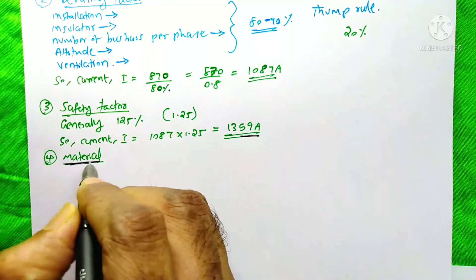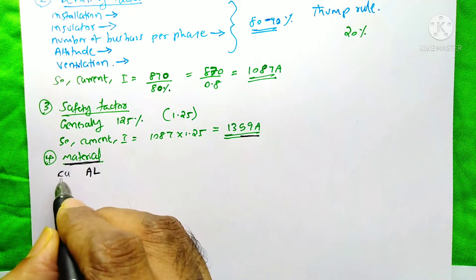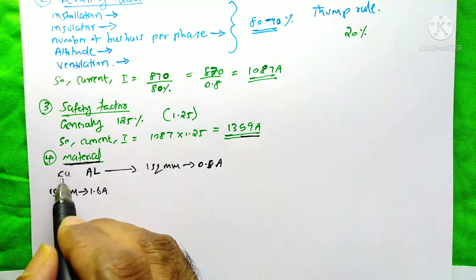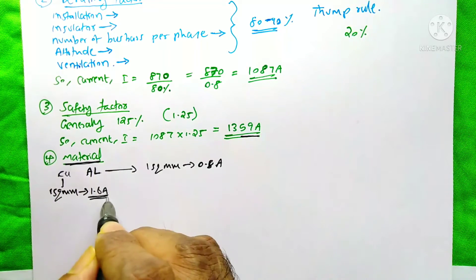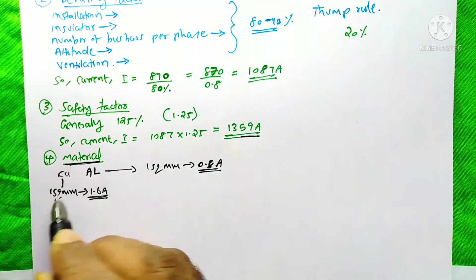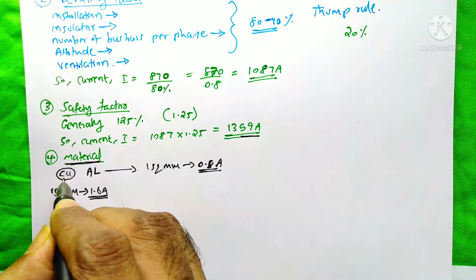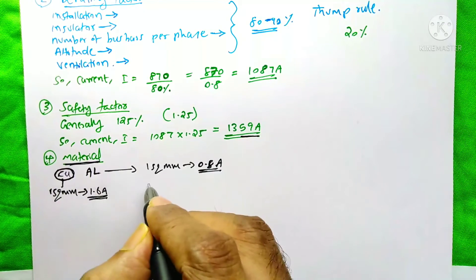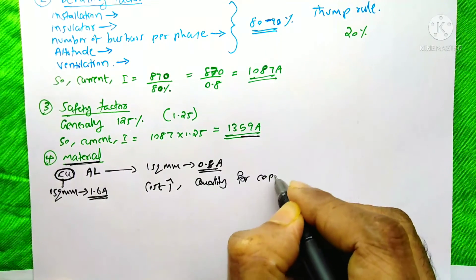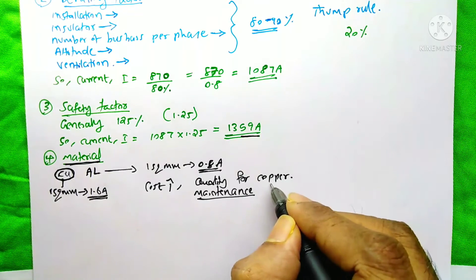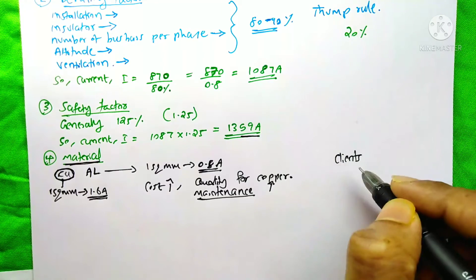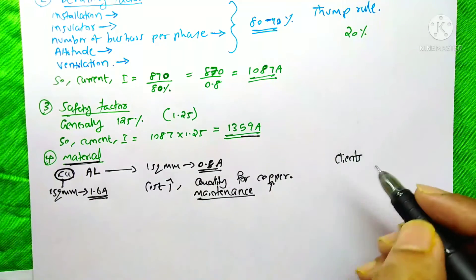The next step is selecting the material for the bus bar. In industry we generally use copper or aluminum. One square mm of copper has a current carrying capacity of 1.6 amps, while aluminum has only 0.8 amps. I suggest using copper because, even though the cost is slightly higher, the quality and maintenance advantages are better.